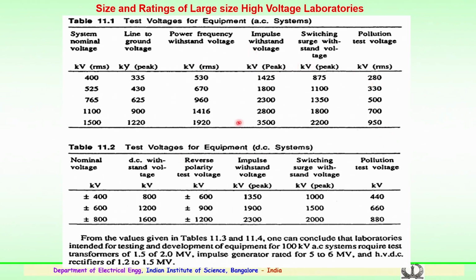So, that is for AC systems. In case of DC systems you can see the table which shows test voltages for various equipments with the DC stress. In case of plus minus 400 kV nominal operating voltage, the DC withstand voltage should be 800 kV, twice the nominal operating voltage, and the reverse polarity test voltage for a 400 kV nominal system should be plus minus 600 kV. The impulse withstand voltage is 1350 kV, the switching surge withstand voltage is 1000 kV, and the pollution test voltage is 440 kV. It is much higher in comparison to the AC 400 kV systems. It is almost twice the level which is required.